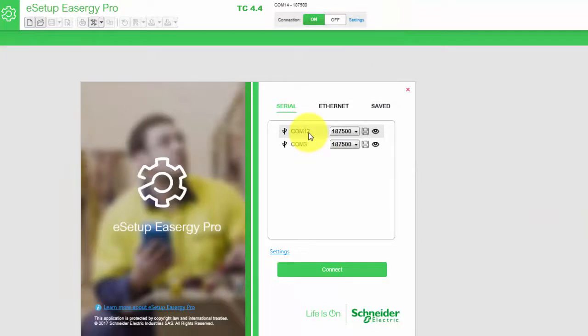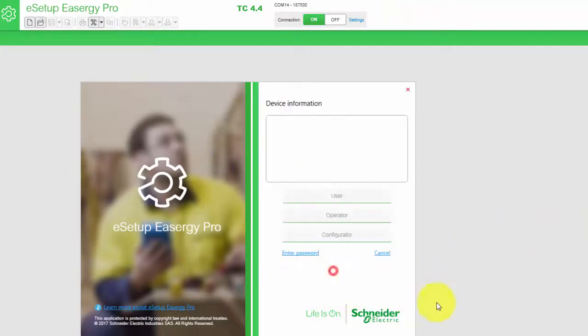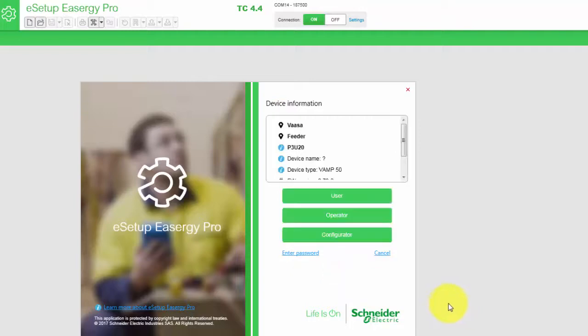We will see that USB Serial Port COM12 has been reserved for the relay connection. After that we will select COM12 and press Connect. The program will automatically read device information from the relay so we will see which relay we are going to connect to. At the same time we can define whether we will connect at user, operator, or configuration level.